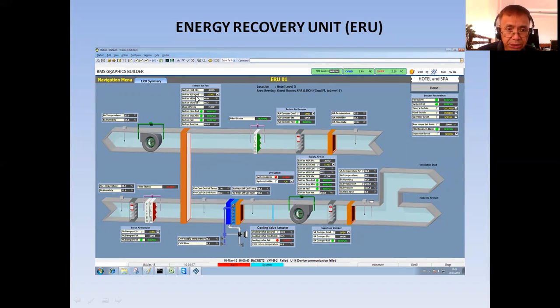Then I'm monitoring the typical control and monitoring points for a fan, like hand, off, auto, run, trip. Then it is controlled by a VFD, so I'm showing also the control signal for the VFD and the feedback status of the VFD. Likewise, the same points for this supply fan. Now, as you can see here, this one is the airflow monitoring. Okay. Now I have the filters. I have a pre-filter and bag filter. Pre-filter also here. Okay. Now in the return duct, the mechanical people installed one pre-filter to make sure that there is no debris going into the heat pipe. Okay. Now I'm monitoring also the ambient temperature.